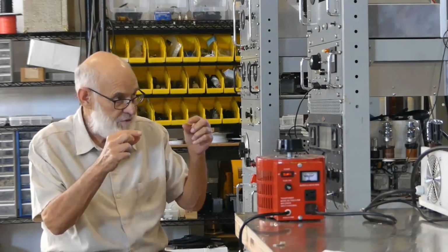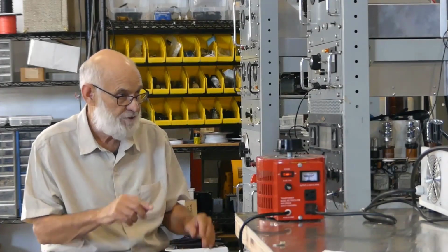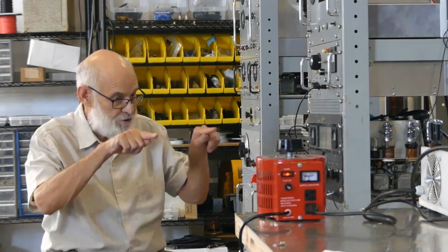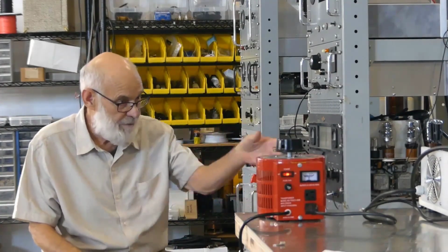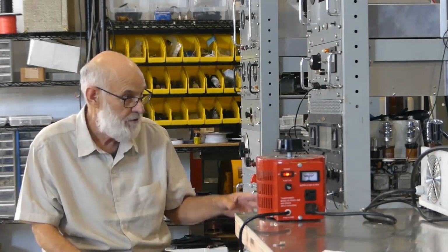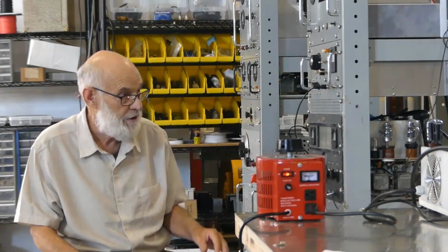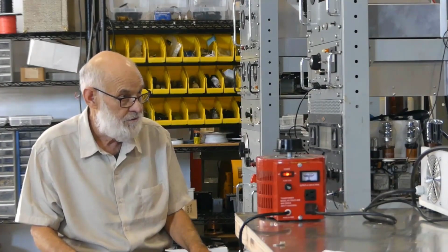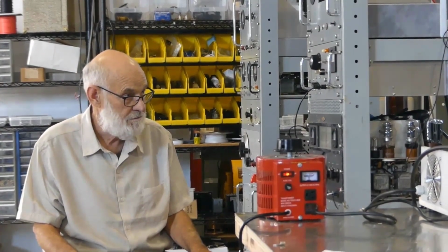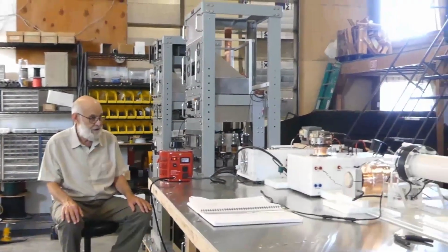Then I have an inductive discharge dissipation, a capacitor resistor series that goes across the contacts, so any back EMF from any coils or what have you doesn't want to keep that arc going and damage the relay. And those ballast resistors, they'll be in series with each of the relays' contacts. Yeah, each contact, yeah.